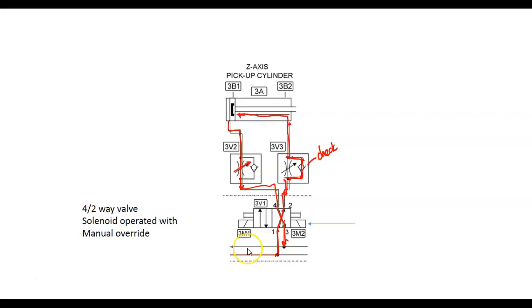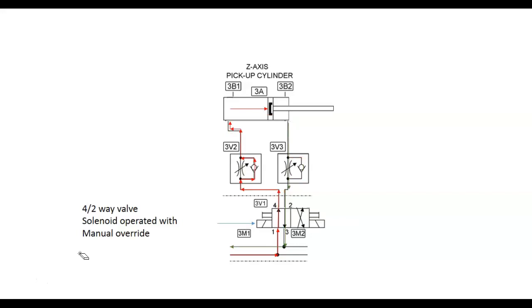So let me erase all this. So what happens is we energize the other solenoid, and this is what you've got to picture in your head. You've got to picture what? The whole thing doing what? Shifting. It's not going to shift on the diagram, but that's what you've got to picture. And I did that, by the way. It took me a long time to get the things lined up. So if I energize this solenoid, it shifts to the left. I energize this solenoid, it shifts to the right. It's going to be drawn in its power off condition. So that's the way the valve is going to be drawn.